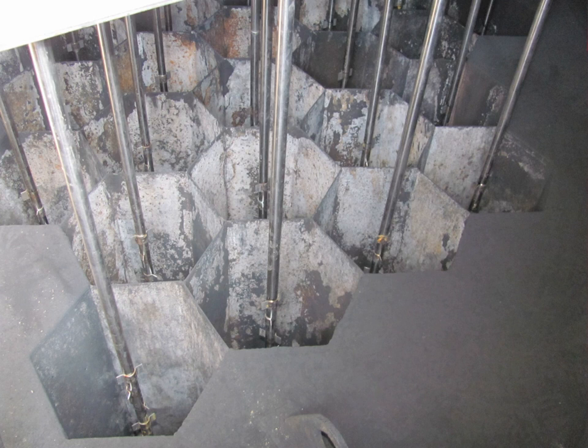Topic: Wet electrostatic precipitator. A wet electrostatic precipitator (WESP) or wet ESP operates with water vapor saturated air streams, 100% relative humidity. WESPs are commonly used to remove liquid droplets such as sulfuric acid mist from industrial process gas streams. The WESP is also commonly used where the gases are high in moisture content, contain combustible particulate, or have particles that are sticky in nature.